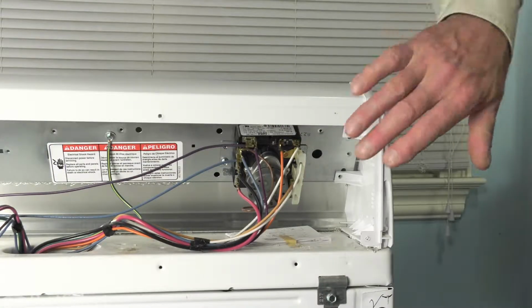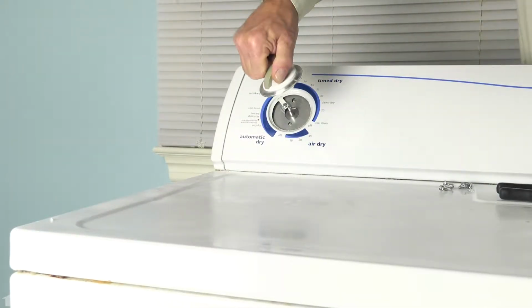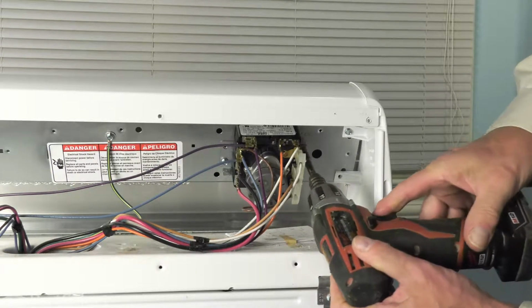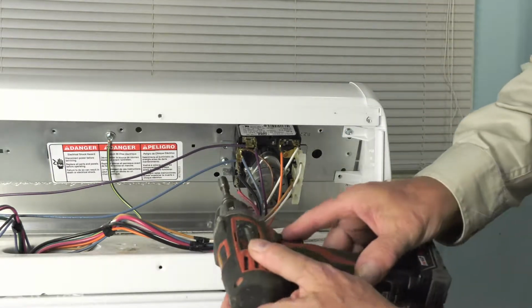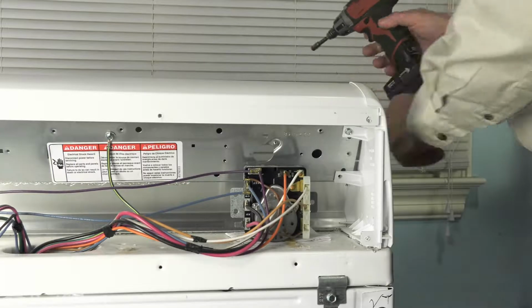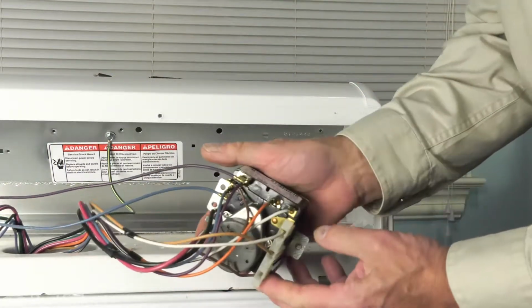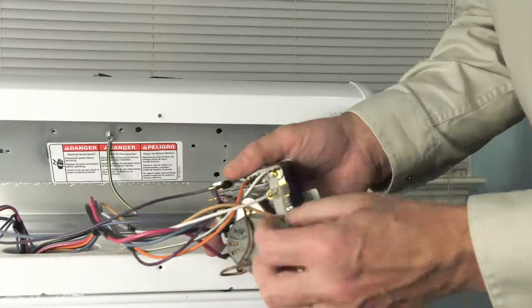Now before we pull the timer off, first thing will be to pull the knob off from the front. So to remove the timer knob, we'll simply just pull it straight off of the shaft. Then next we're going to remove these 1/4-inch hex head screws that secure the mounting bracket to the control panel.